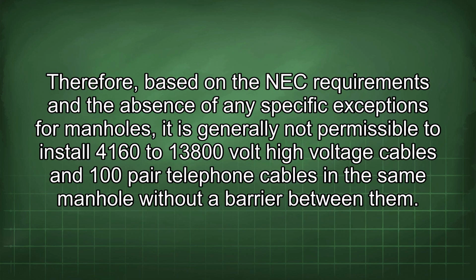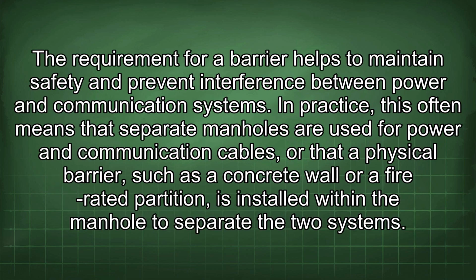Therefore, based on the NEC requirements and the absence of any specific exceptions for manholes, it is generally not permissible to install 4,160 to 13,800 volt high voltage cables and 100 pair telephone cables in the same manhole without a barrier between them. The requirement for a barrier helps to maintain safety and prevent interference between power and communication systems.